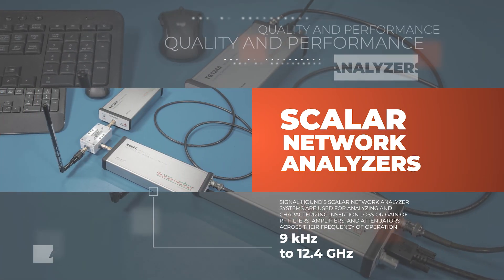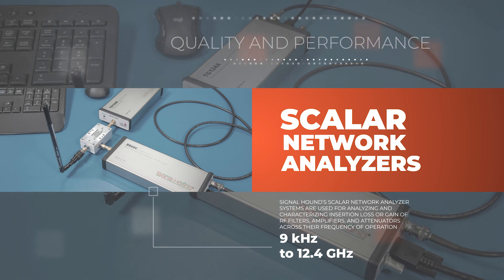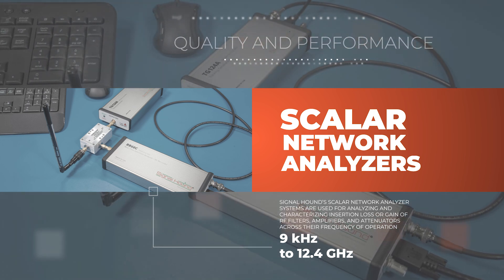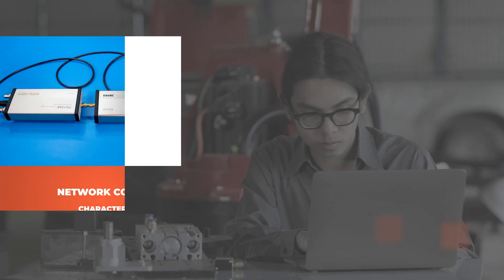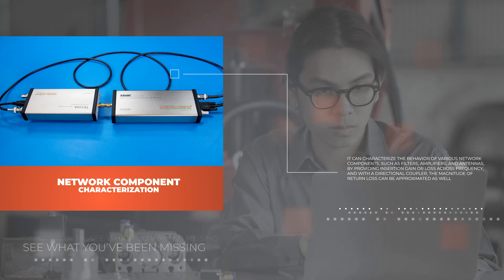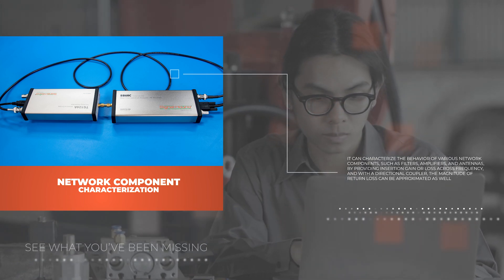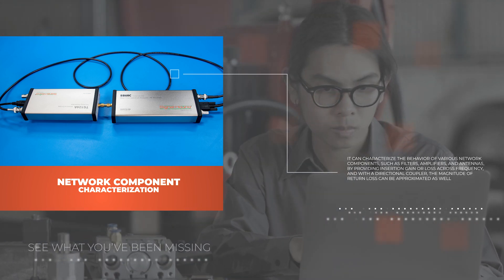SignalHound's scalar network analyzer systems are used for analyzing and characterizing insertion loss or gain of RF filters, amplifiers, and attenuators across their frequency of operation. They can characterize the behavior of various network components such as filters, amplifiers, and antennas by providing insertion gain or loss across frequencies. And with a directional coupler, the magnitude of return loss can be approximated as well.